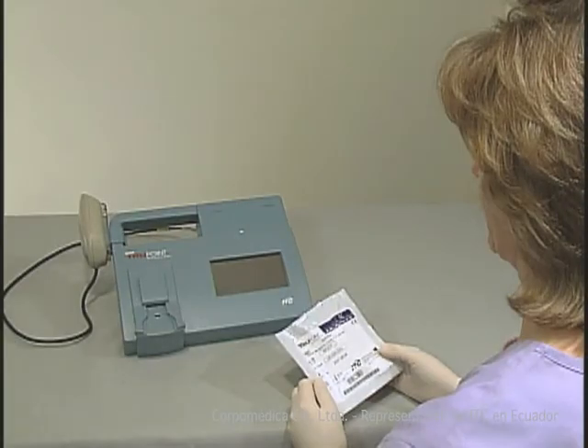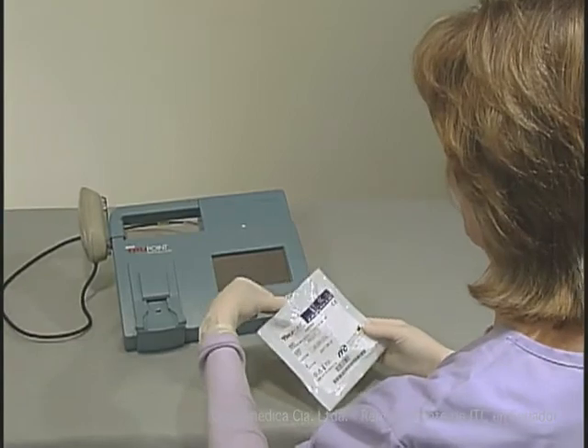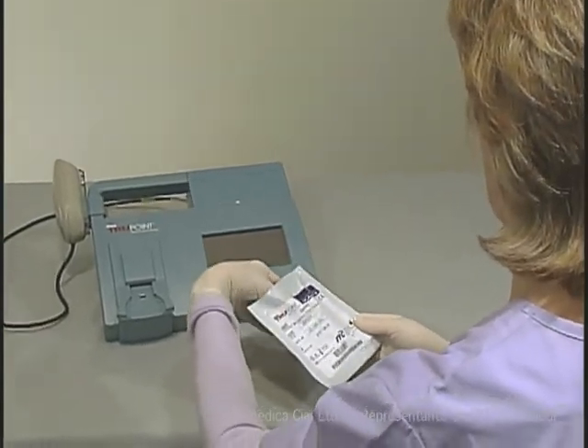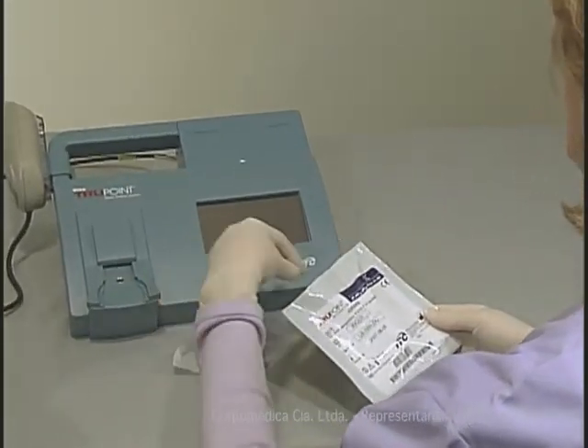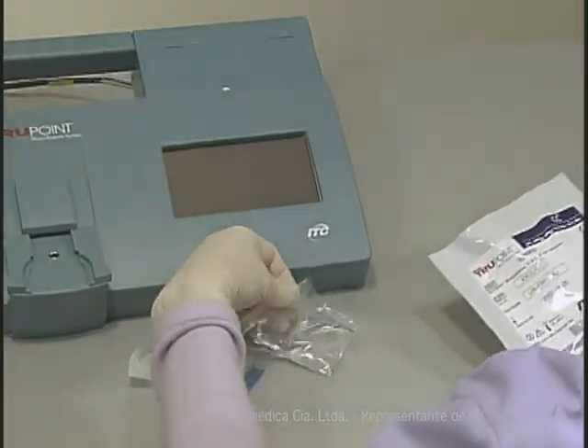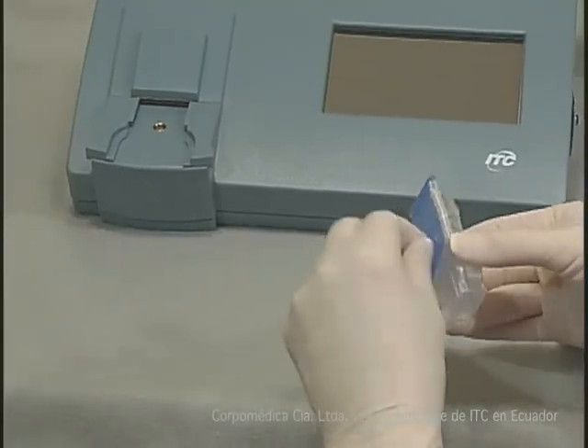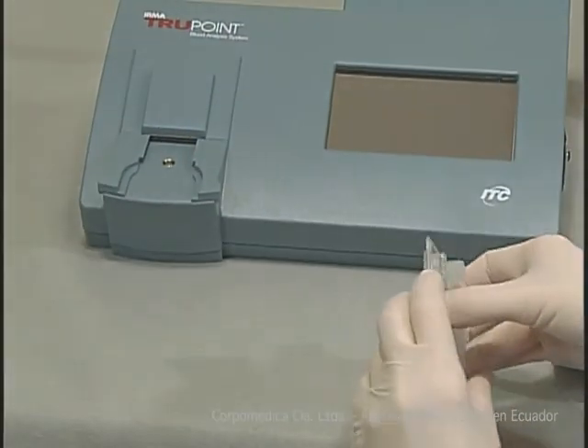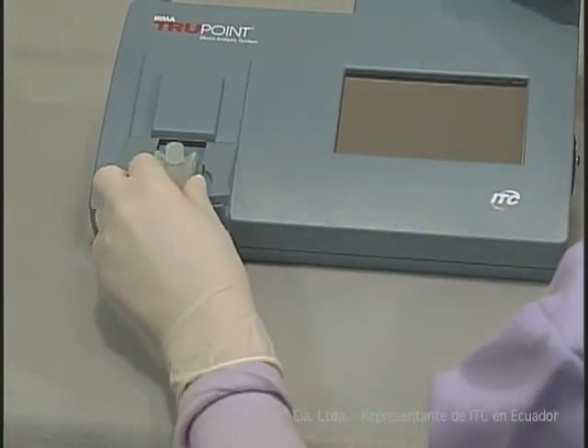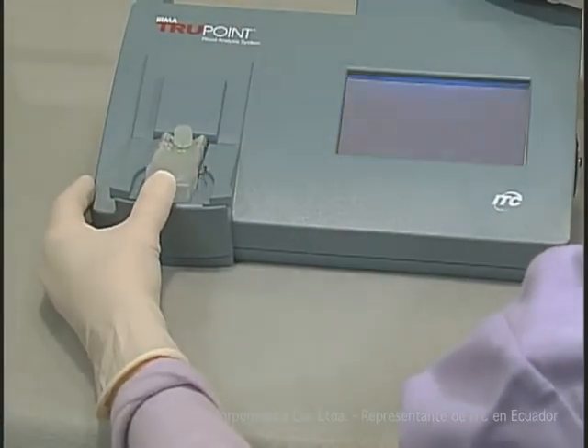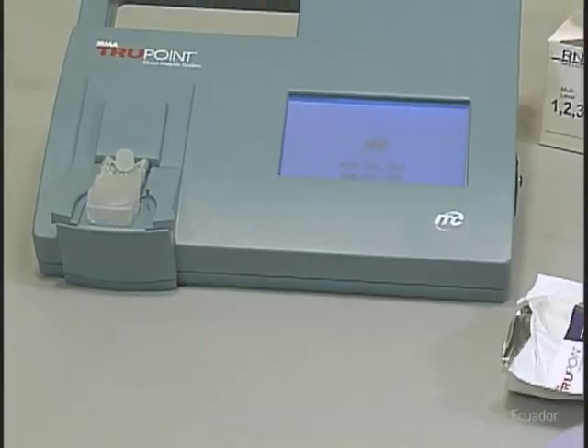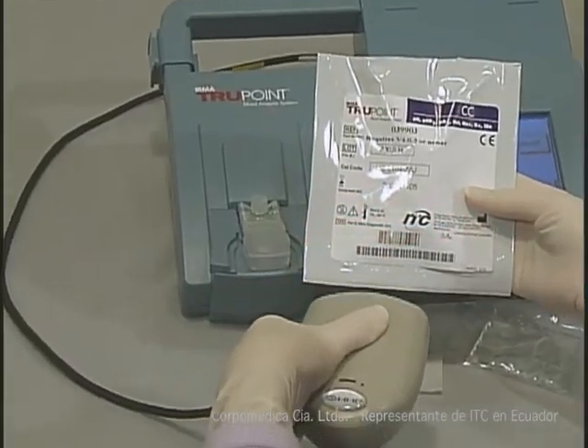First, remove the cartridge from the pouch. If blood gases are being run, the pouch will also contain a reservoir bag and filter paper. Remove the blue protective tape from the cartridge leads. Insert the cartridge into the analyzer and follow the screen prompts. Verify or enter the lot number and cal code, either manually or with the optional barcode reader.